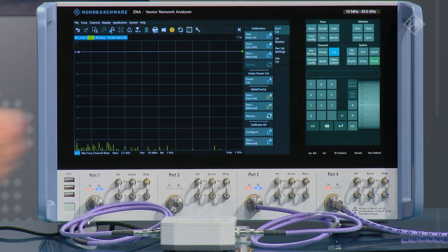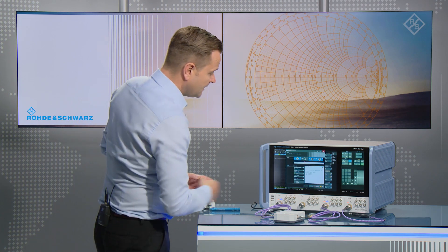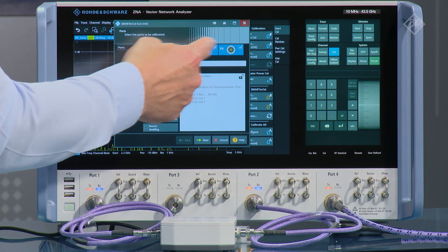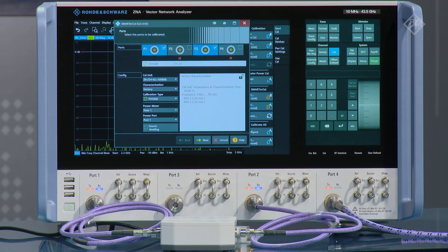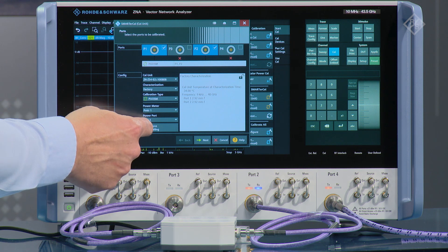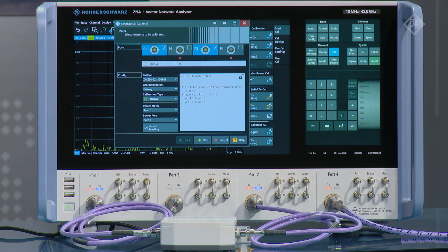In the CAL menu we're choosing a specific calibration routine called SmarterCal. The SmarterCal routine combines the S-parameter calibration and the power calibration together into a simple routine that means I only have to connect each of the standards once. Here we can see that we're calibrating port one and two. I'm going to omit port four, which is our LO port in this particular case, just to speed things up. At the bottom we can see that we're going to connect the power meter to the reference port one, and we can also choose source leveling to make sure that we get maximum flatness on the source output.